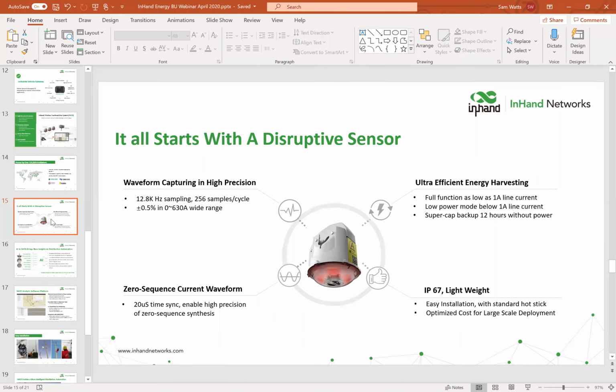To dive in a little bit, the sensors are lightweight—a little less than 2 pounds—and clamped securely onto the line. As I mentioned earlier, they feature full functionality mode as low as 1 amp line current, and will actually continue working below 1 ampere down to about 0.3 amps, just picking up ground faults and limiting the cycles of reporting a little bit.